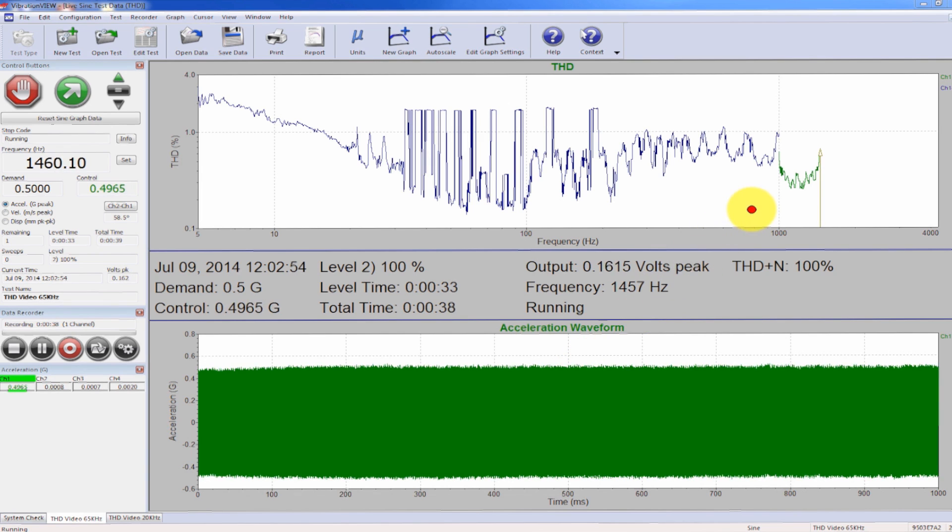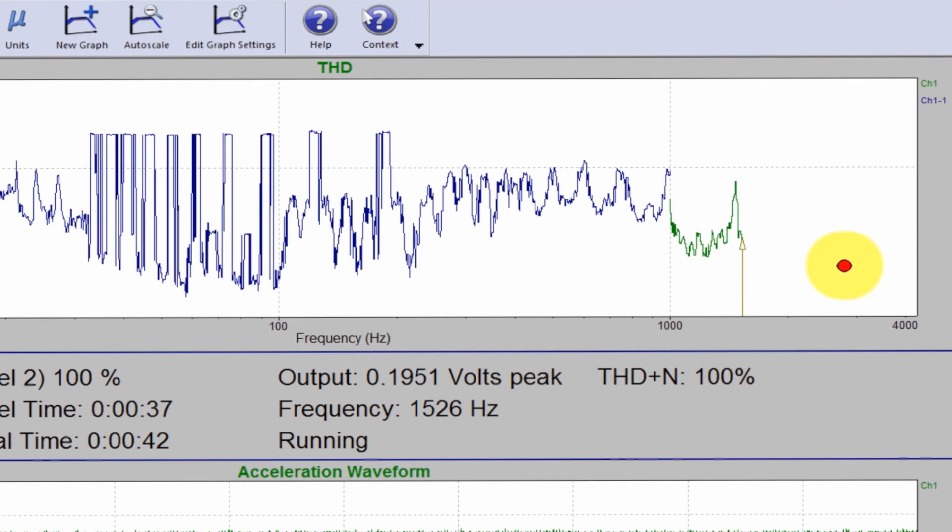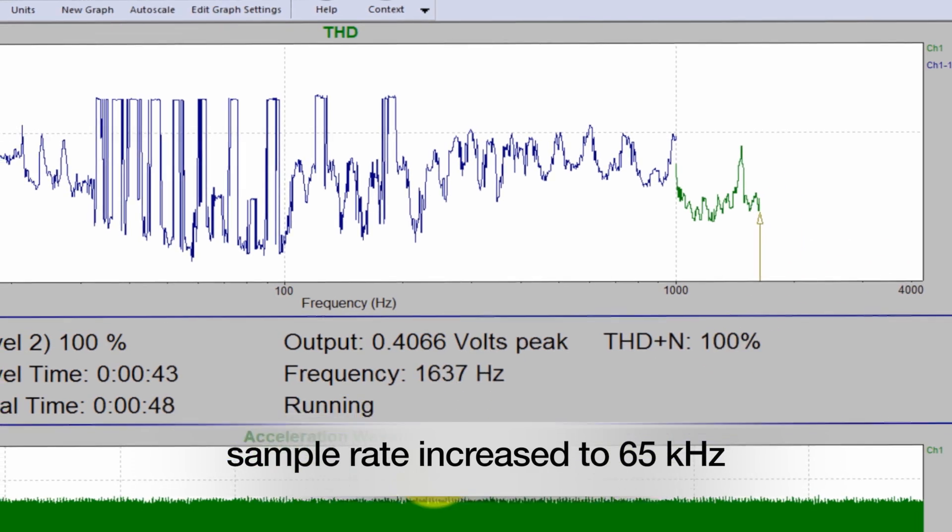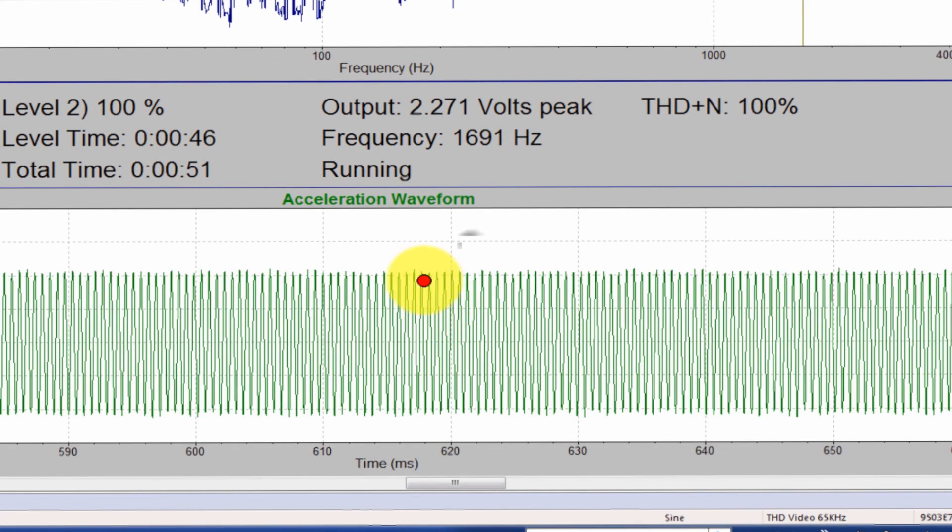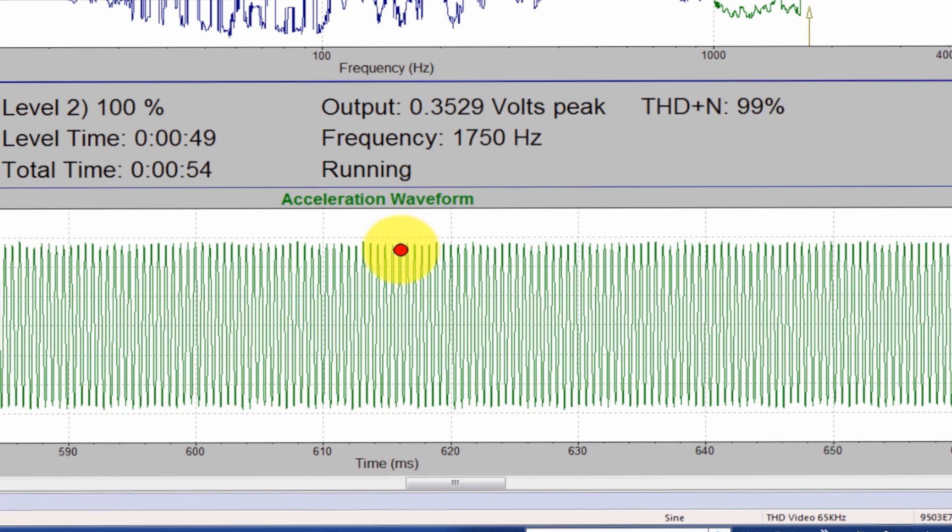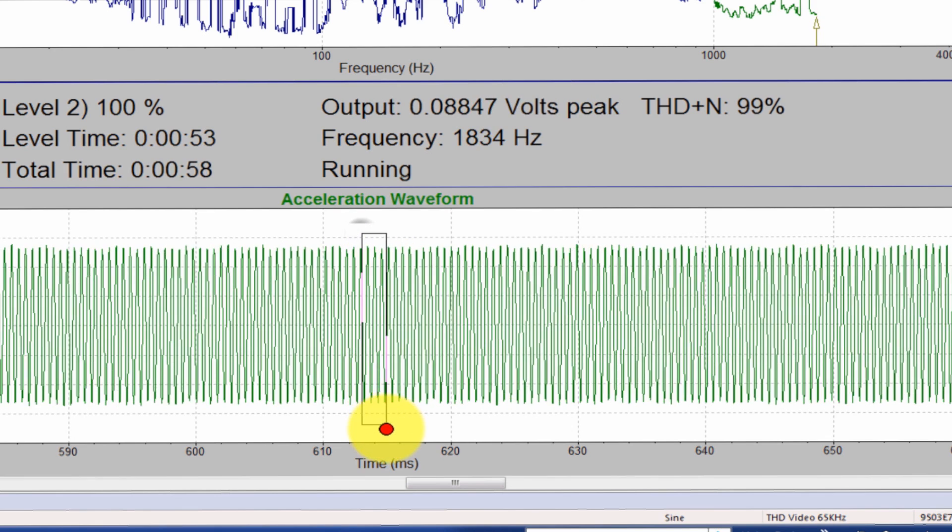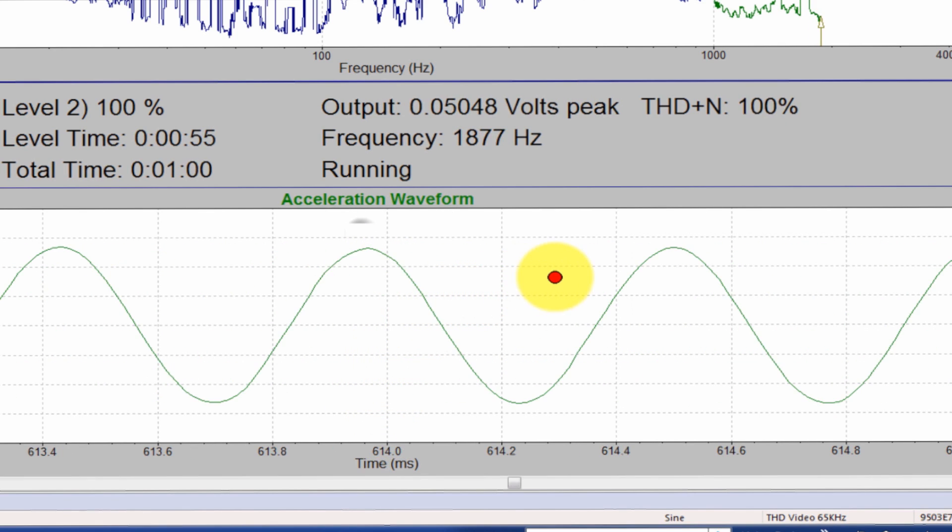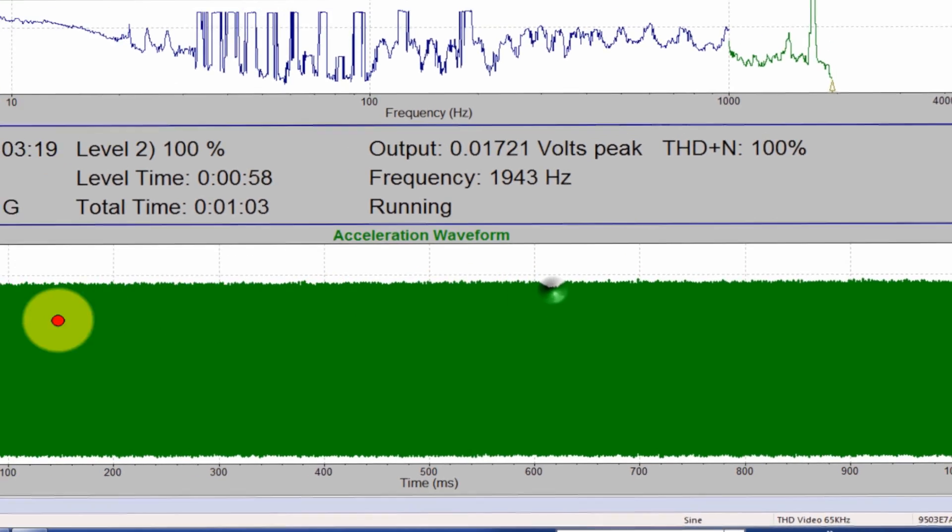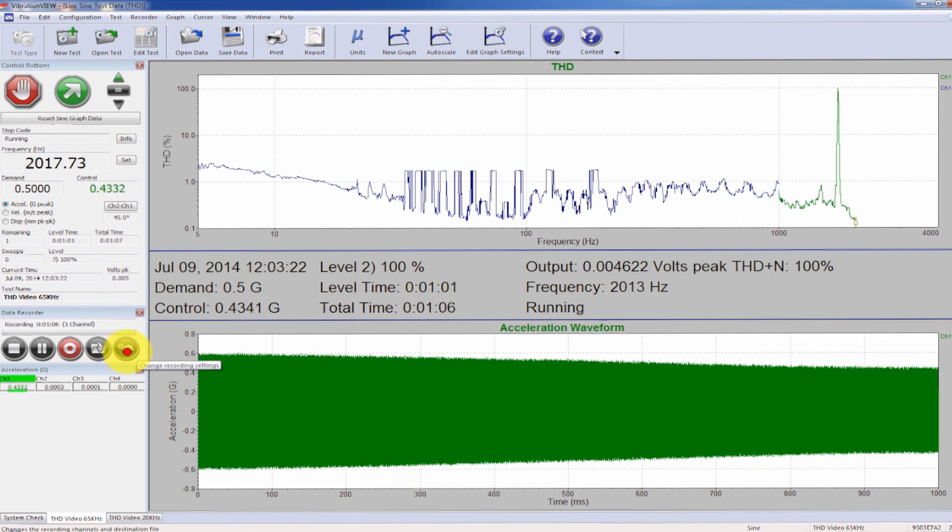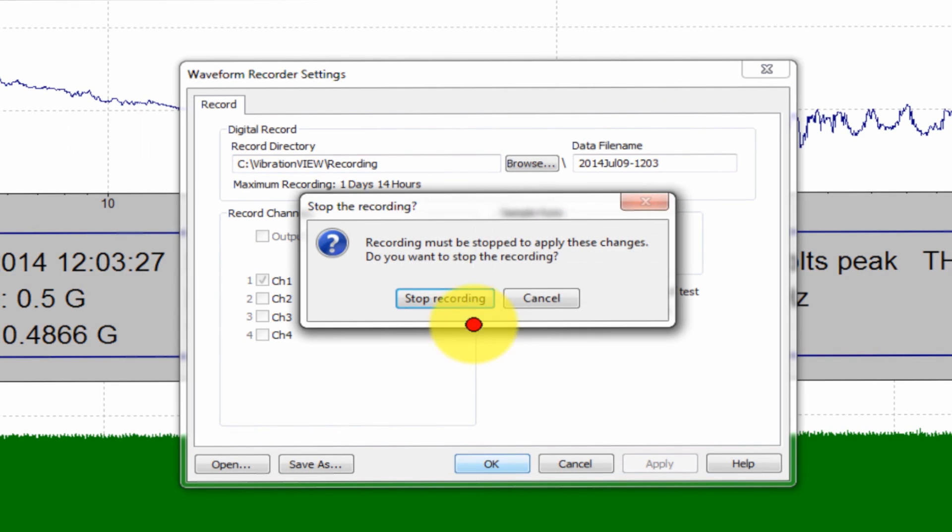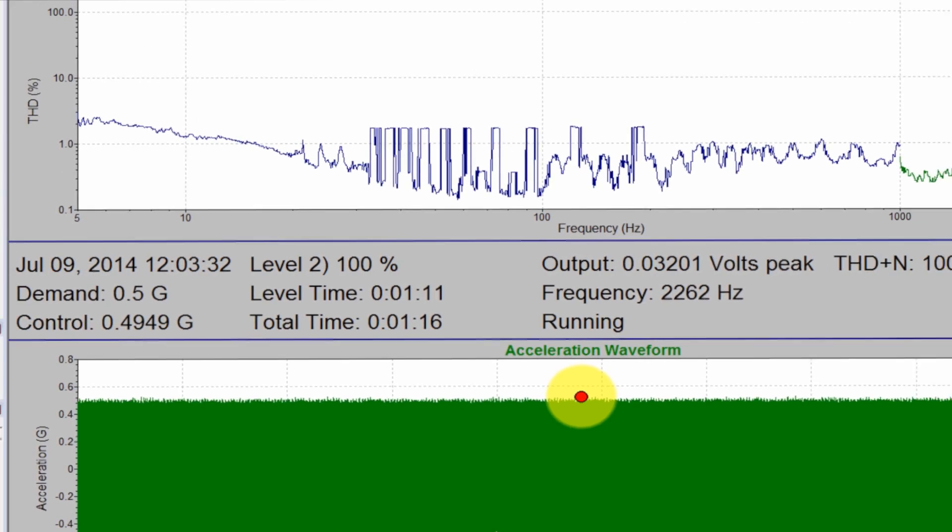So here I've completed my sweep up to a thousand and I'm actually running out to four thousand hertz now or four kilohertz. And I've increased my sample rate to 65 kilohertz. And you can hear that we just hit a resonance or mode of the head expander or the system. And again, if I zoom way in here, you can look at the actual waveform. Now I'm actually recording this waveform as well. So I have the system configured to record channel one during the test.